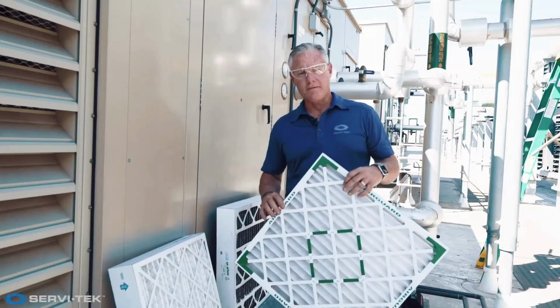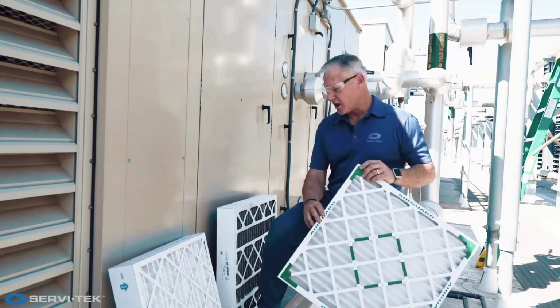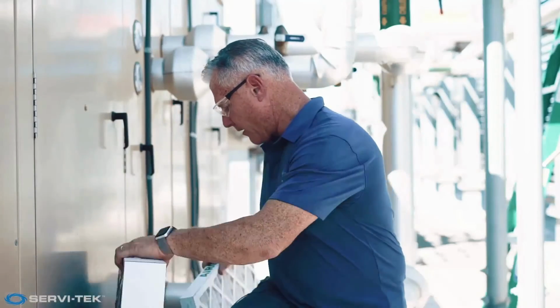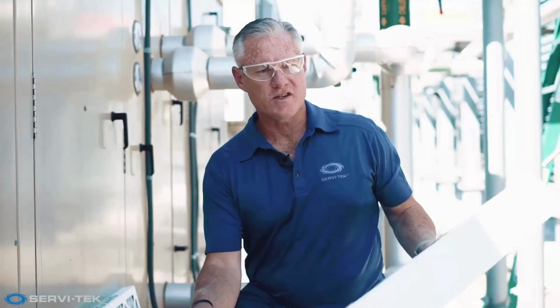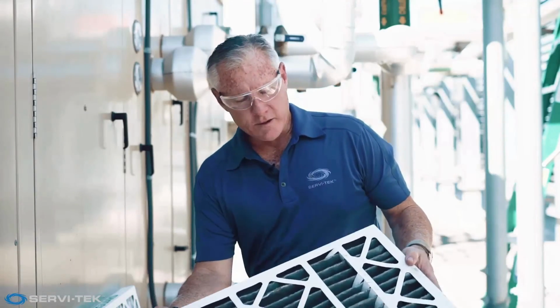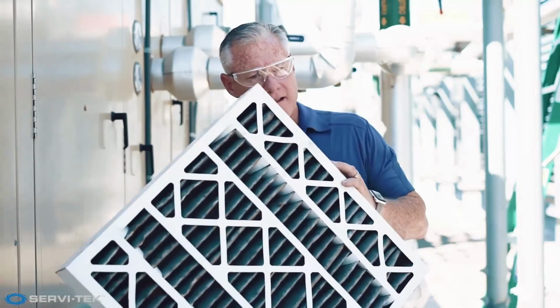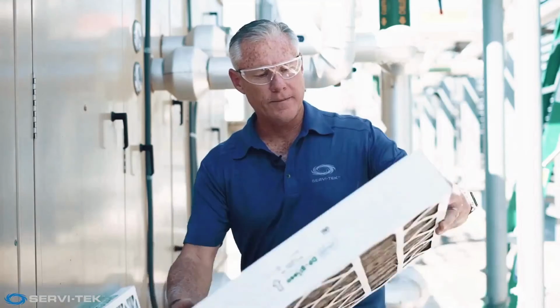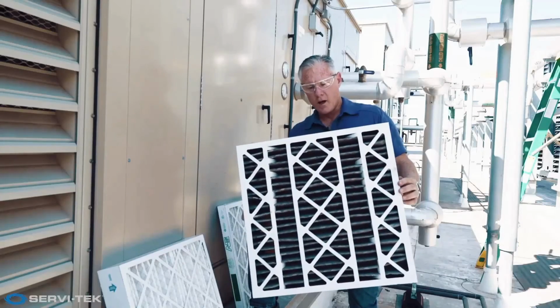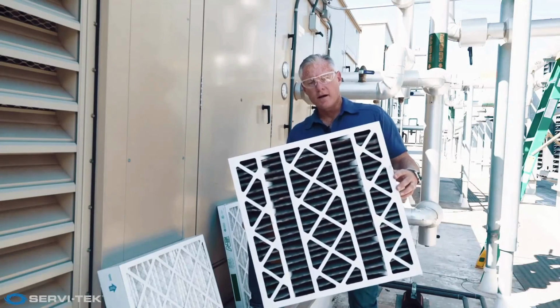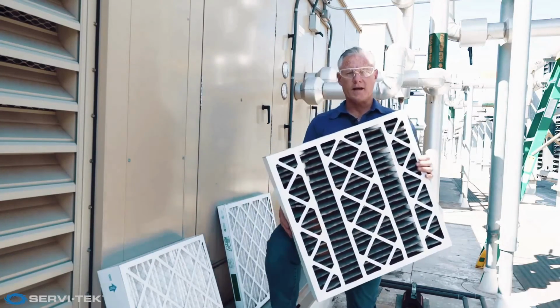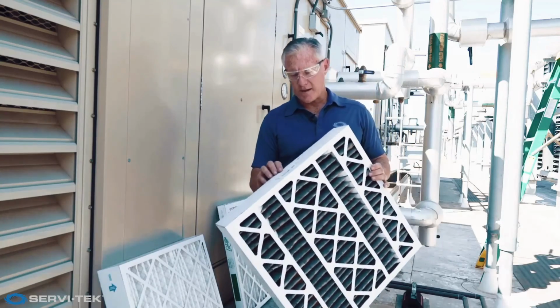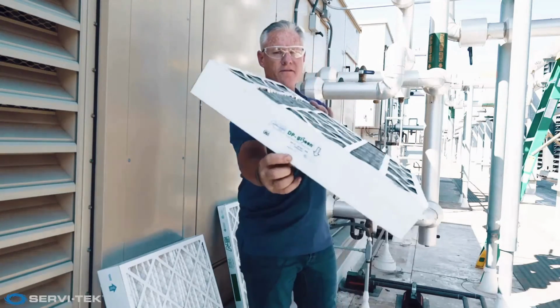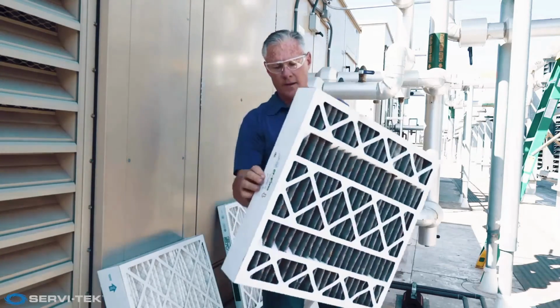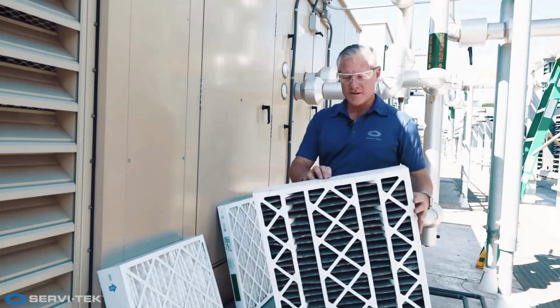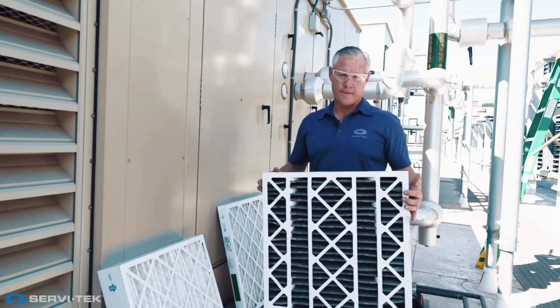Now, let's talk about filters for a second as far as changing goes. Often people say, how often should I change filters? And they'll see a filter that looks something like this, a little bit gray, a little bit dirty, and I'll say, well, why are you changing that? And they'll say, well, we change them quarterly just because. Okay, well, these are kind of expensive, as you'll see here. This is a MERV 13 rated filter. MERV 13s are pretty expensive filters these days, and they're a little bit hard to come by.